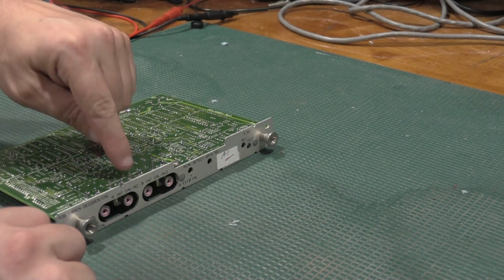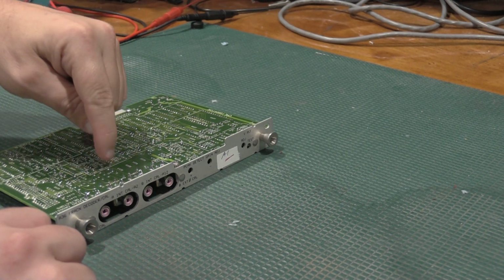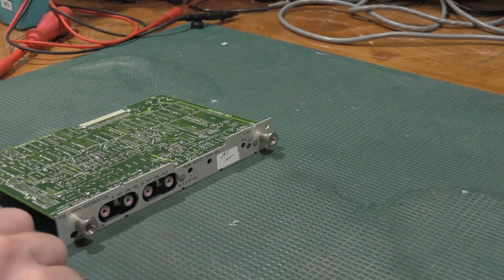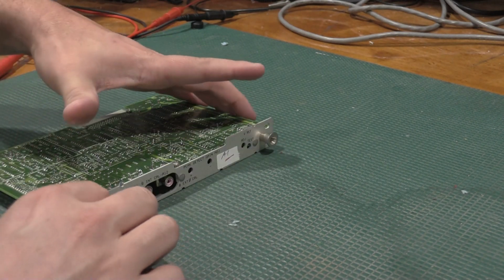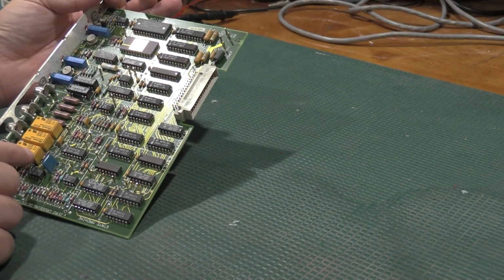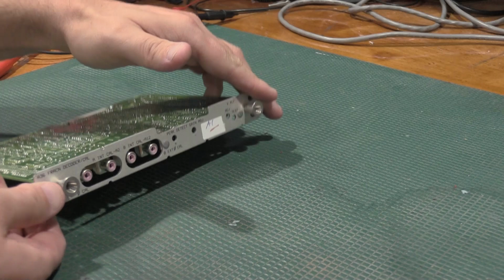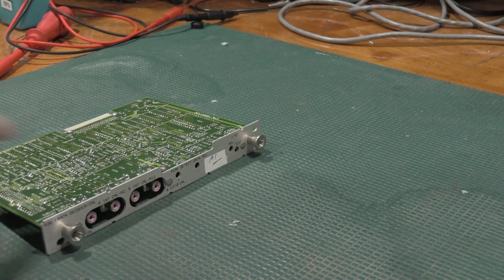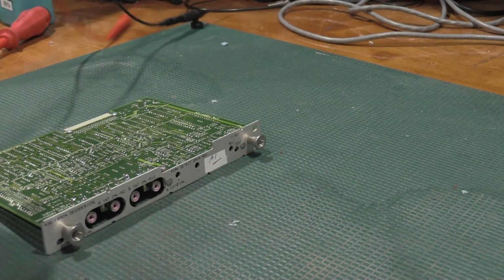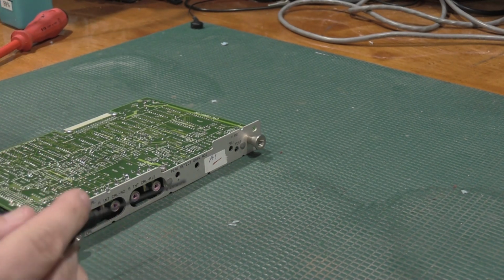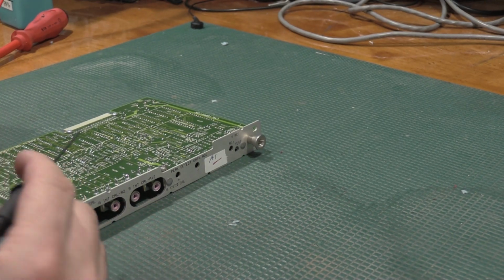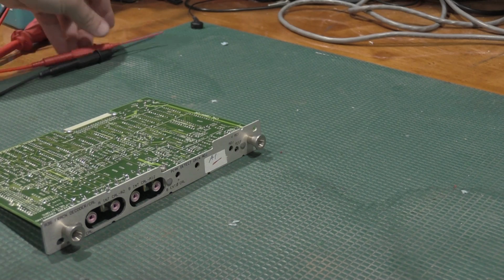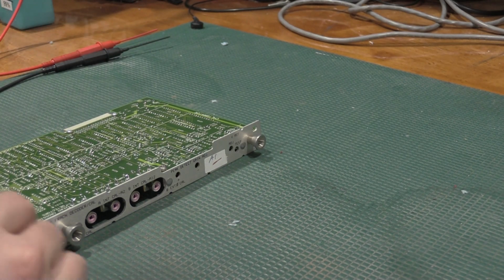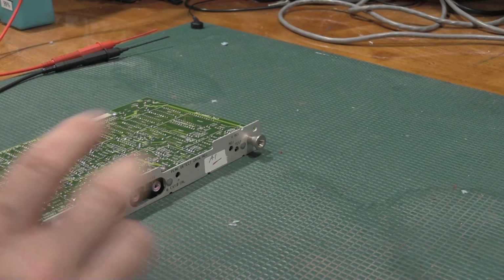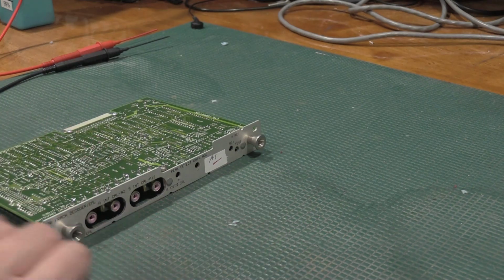Okay, so here are our relays in question. We have an 8-pin combination, 3 contacts and the coil, 2 poles on each relay. Coil's off to the right, in this case the pins furthest away from the line. The line denotes the normally open and normally closed. The center 2 are the normally closed. The outside 2 are the normally open. So we're going to check the normally closed relay contacts for dead shorts. I'm looking for below an ohm, really low contact resistance on these relays, especially given that our fault is around a volt. Too much resistance in the relay is going to throw it off.